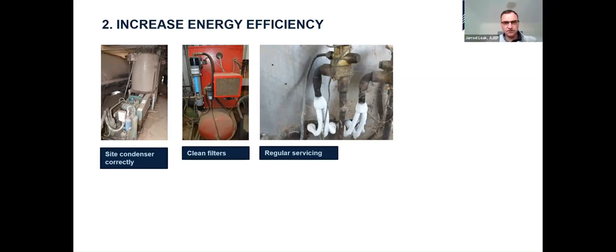Absolutely, Gavin, I'll concur there. I was out at a dairy farm last week, with spider webs and dust all over that condenser. It's about a 10-minute job to take the grate off and brush it down with a short handle brush, making sure you're not going to cut yourself on those fins. They can be quite sharp. A 10-minute job, and we had that thing looking like new, and that would greatly improve the heat transfer and the efficiency of that refrigeration system.